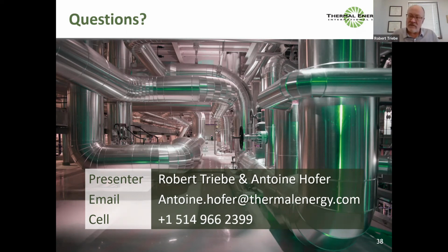You cannot tell them how much they're going to save based on the efficiency of the unit. Yeah, that is a very good question. The way that we would tell them how much they save is either an hourly or daily model of return temperatures to the unit. With those daily or hourly return temperatures, you know exactly the performance you get at that point in time, and that's how you model savings. But you can't possibly say your steam boiler's 80%, and under this average condition we expect 90%, and here's your savings. You want to build the case, you have to model.